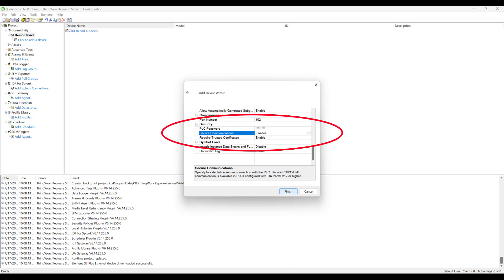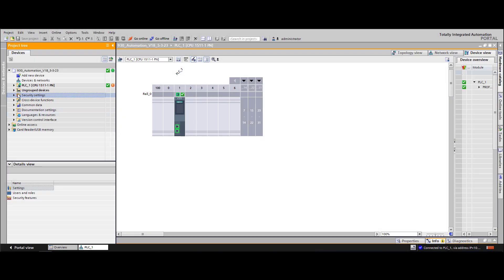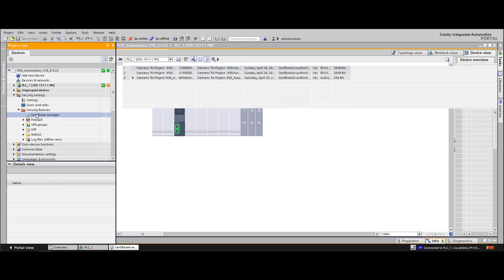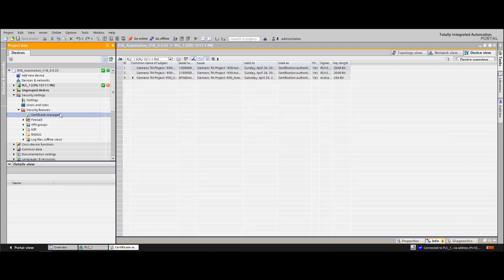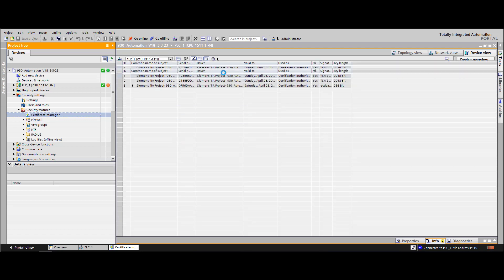When using these options, the trust certificate must be manually imported into the Siemens S7 Plus Ethernet Trust Store. The certificate can be found by opening TIA Portal and navigating to Security Settings, then Security Features, then Certificate Manager. From here, we can export the certificate.